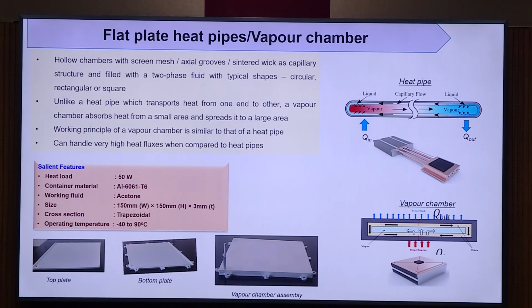There are flat plate heat pipes or vapor chambers. These are hollow chambers filled with screen mesh or sintered wick or any axial wick, which acts as a capillary structure, and filled with a two-phase fluid. It can be circular, rectangular, or any square shape. Unlike a heat pipe, which transports heat from one end to the other, a vapor chamber absorbs heat from a small area and spreads it across a large area. Basically, it reduces a high heat flux device to a low heat flux device.